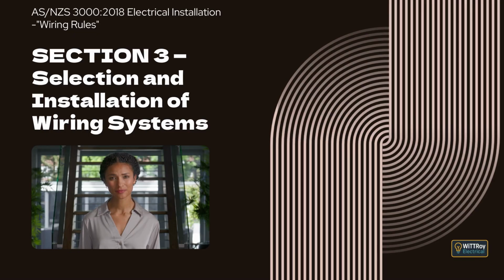Clause 3.7.2.1.2, Aluminium conductors. This clause explains that joints and connections involving aluminium conductors must use components and techniques specifically designed for aluminium. Special considerations include removing aluminium oxide from the conductor, accounting for the softness of aluminium, allowing for different thermal expansion compared with other metals, and avoiding contact with dissimilar metals that could cause galvanic action.